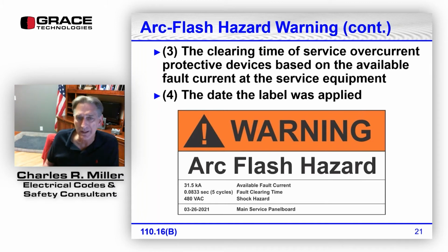So here is a warning label that is one example of a label that this 110.16(B) is referencing. It's giving the available fault current at 31.5 kA, or 31,500 amps. The fault clearing time is 5 cycles. The voltage is 480 volt. It has the date on there, and it specifies what equipment it is, the main service panel board. Now, the date, this is a label I made up. So I typically have dates on there that are important to me.